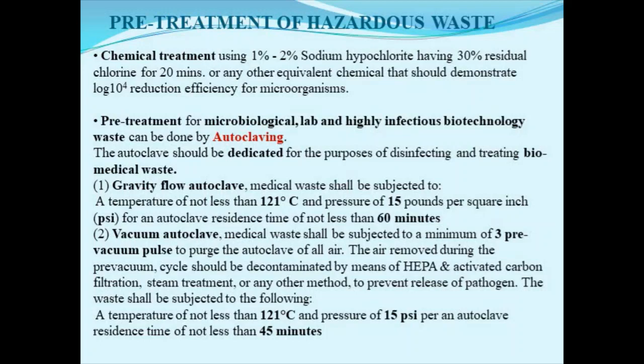Medical waste should be subjected to a temperature of not less than 121 degrees Celsius and pressure of 15 pounds per square inch for an autoclave residence time of not less than 60 minutes. So there are 2 different times. The autoclave heating time is the time to reach 121 degrees Celsius, that is the boiling point of water at 121 degrees Celsius when a pressure of 15 pounds is reached in the autoclave. So that is the heating time.